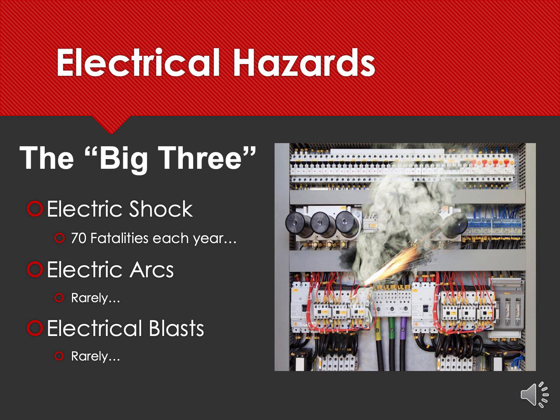The arc flash that you see here is the one that I would expect in an industrial control panel, in that it could be harmful to your hands or your eyes, but it would not normally precipitate the kind of arc flash we're trying to manage with the arc-rated clothing and things that we wear on the job. So in other words, it's going to be up to the worker doing the work to ascertain the shock hazards and the arc flash and arc blast hazards in the workplace. So let's go to the next slide.